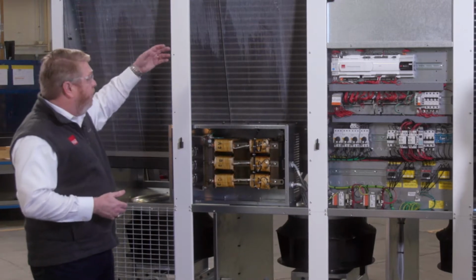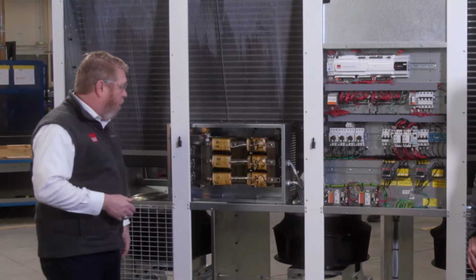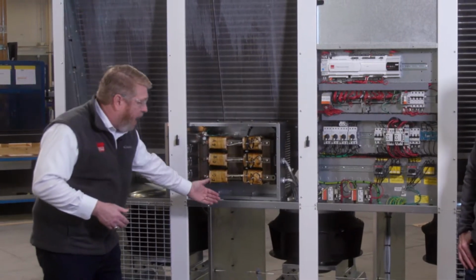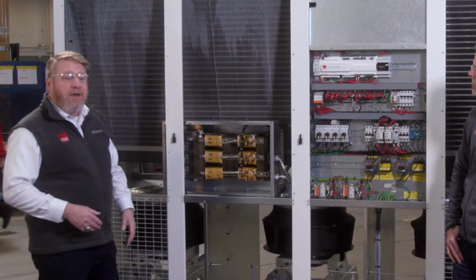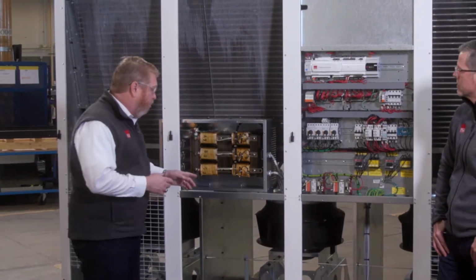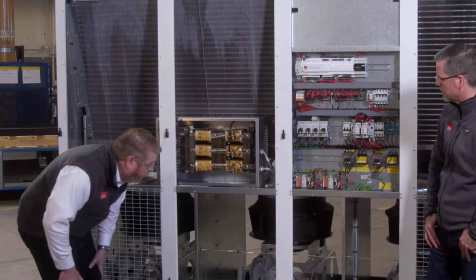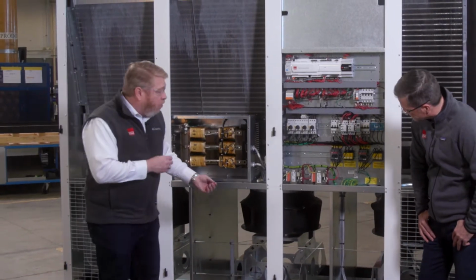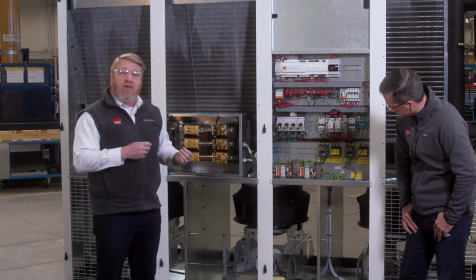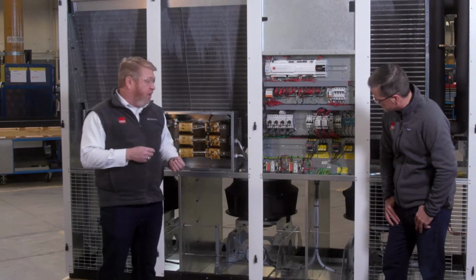And then what we're seeing now is a real demand for what is a downflow unit with a front discharge, and that's what we have here today. So air would be coming in the top, it would be coming down through the cooling coil, and then discharged out the front of the unit. Now, I would like to point out that this model that you see here today has our new composite electronically commutated fans in the unit.